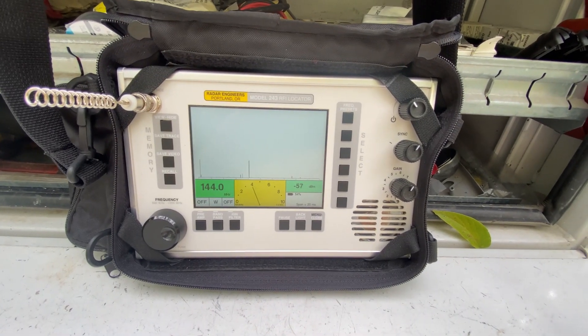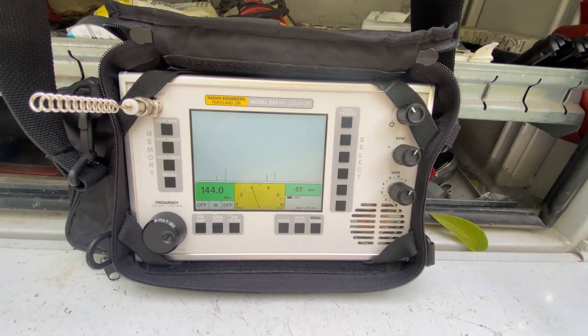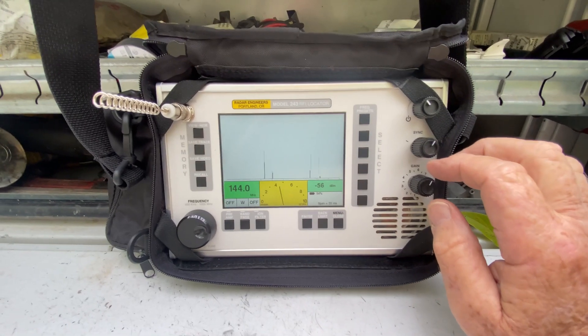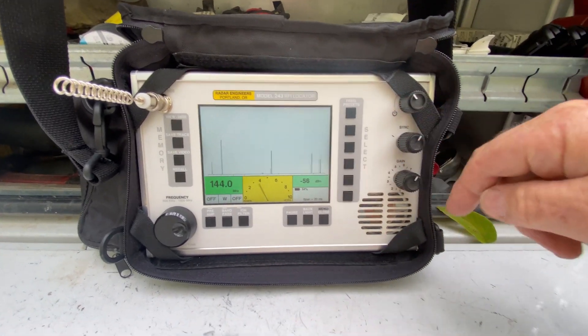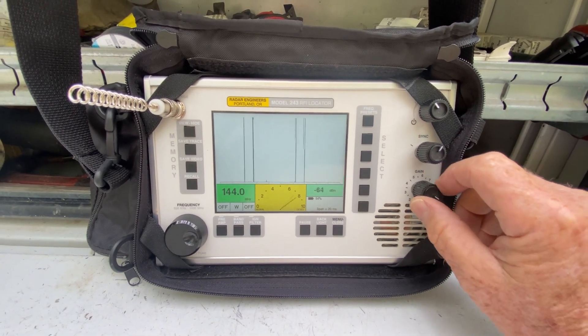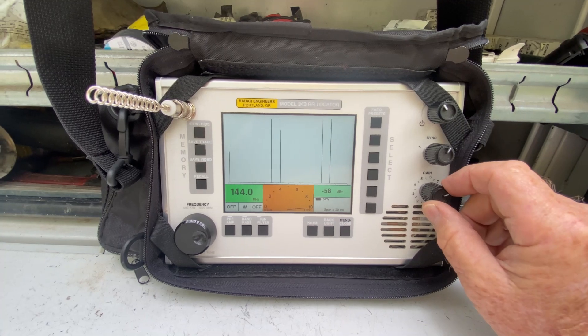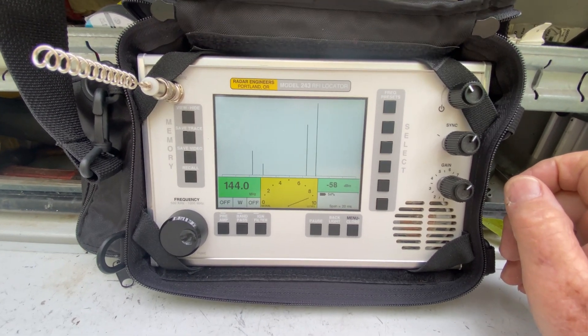You saw the lineman using the sniffer to determine which part on the pole was making the noise. We believe that it's the arrestor. Right now our frequency is 144 and I've got the gain turned down. This would be gain full blast using the radar engineer's 243, so that's at 144. My pre-selector is at 330.